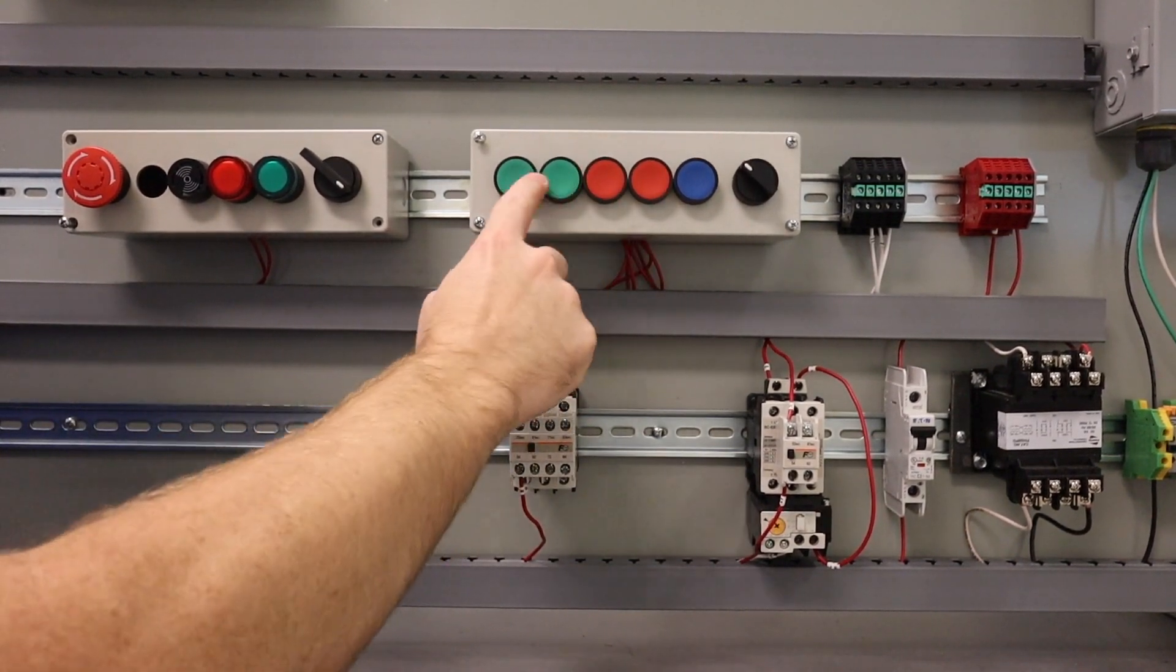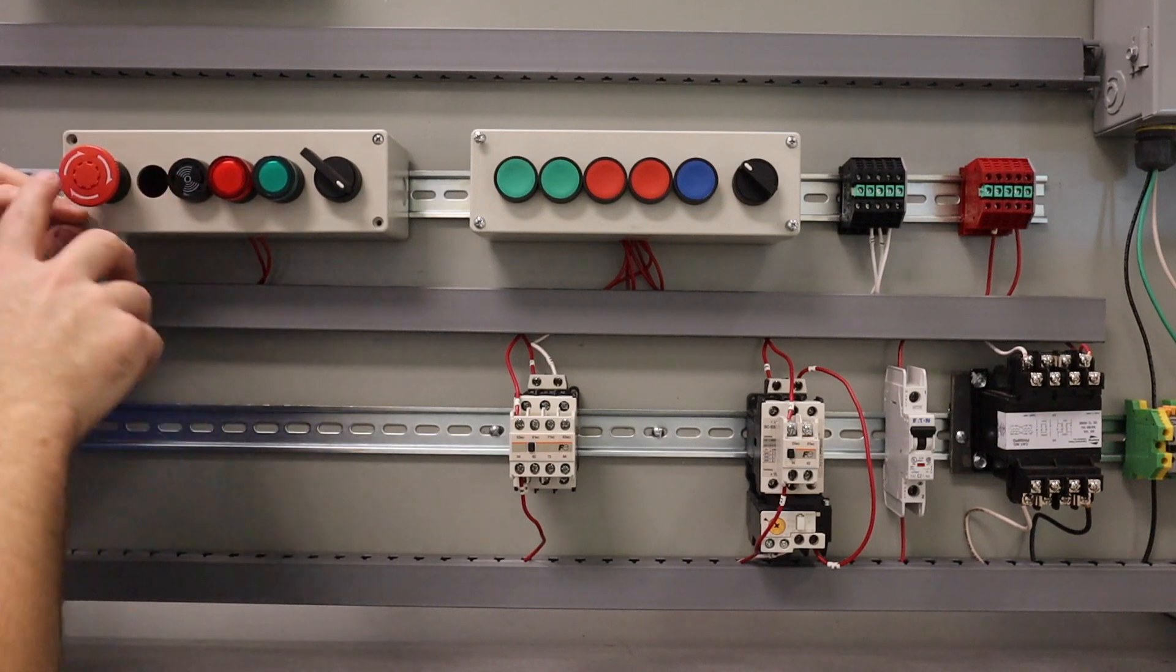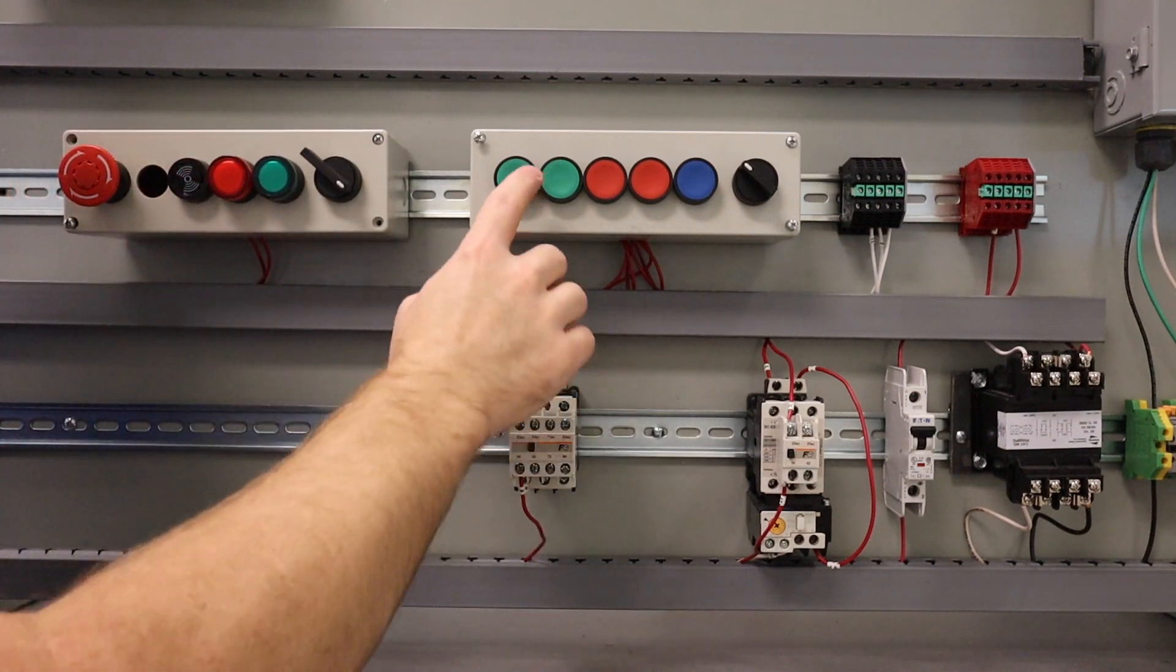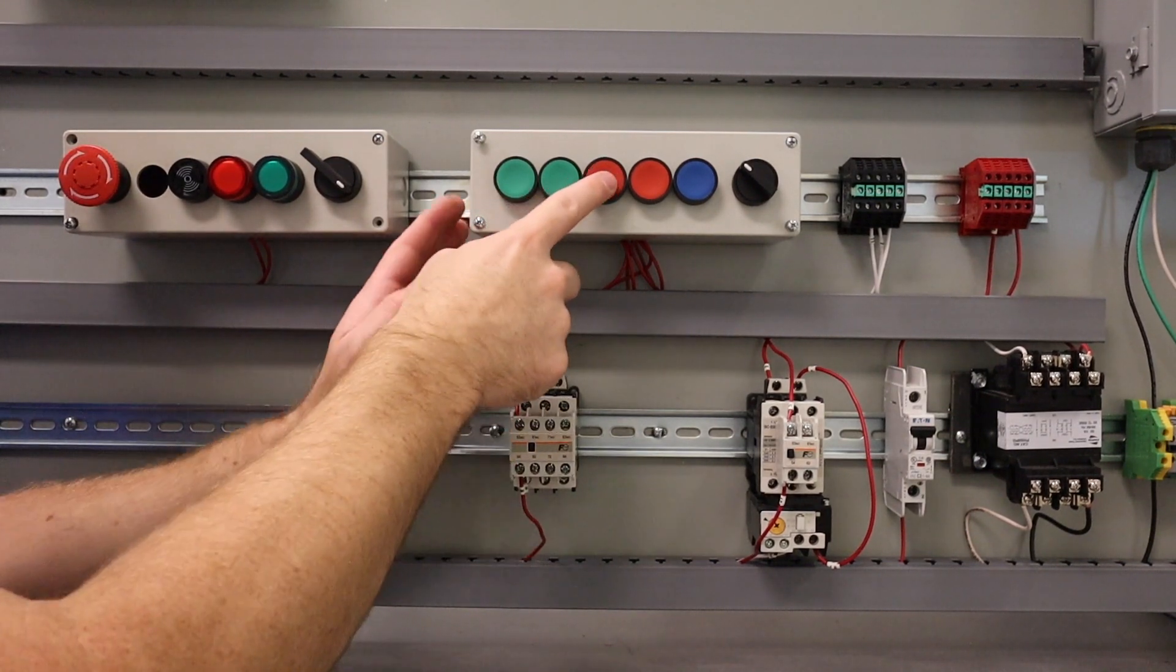I put in my e-stop. If my e-stop is depressed, nothing is going to run. If it is closed - the contacts are closed on it - then I press motor one and it pulls in. If I hit the stop button for motor one, it turns off.